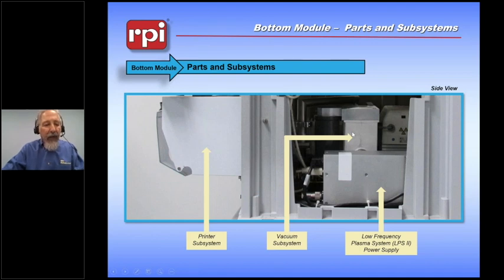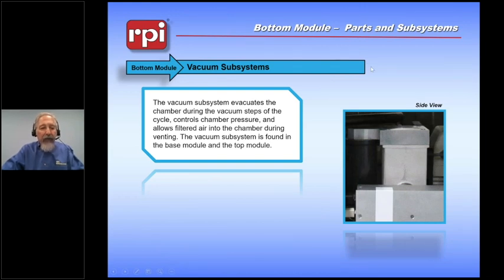We have a coalescing filter that collects any oil that may be getting into the escaping air out of the vacuum pump. And we also have a catalytic converter that will catch any hydrogen peroxide that may have slipped through the plasma process and gotten out with the airstream to this point. The catalytic converter contains a chemical that continues the process of breaking down the hydrogen peroxide. The vacuum subsystem evacuates the chamber, controls the chamber pressure, and allows filtered air in through venting. The vent for allowing air into the chamber is located in the top module.